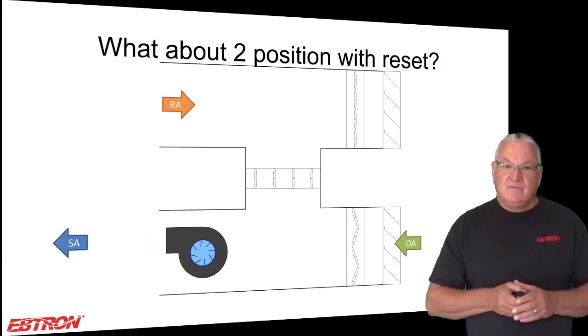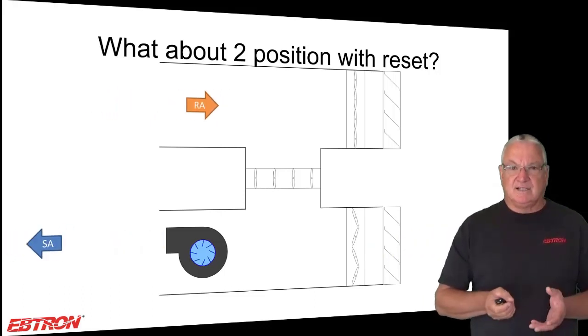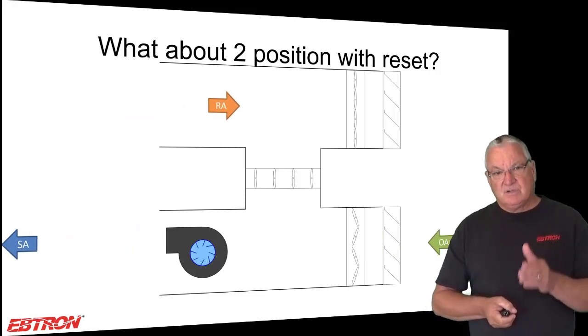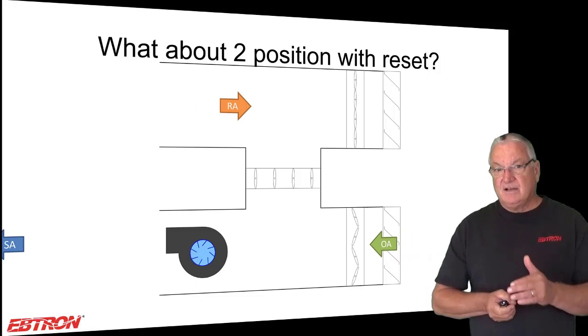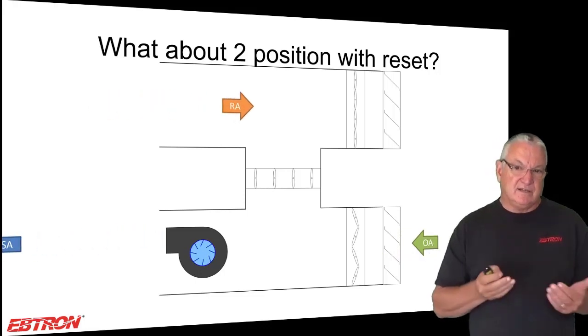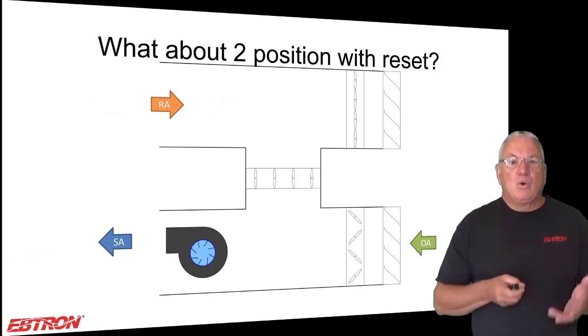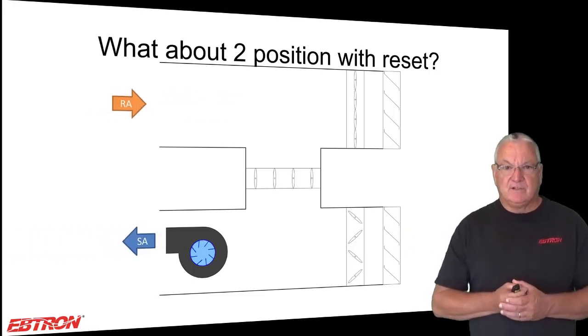First of all, everybody assumes when they're doing this that the damper is linear, and the damper is not linear, but that's the least of my worries. What happens is when we're at this particular condition, which is design airflow, to get in the outside airflow, the damper is in a more closed position than it will be when we reduce the supply flow.